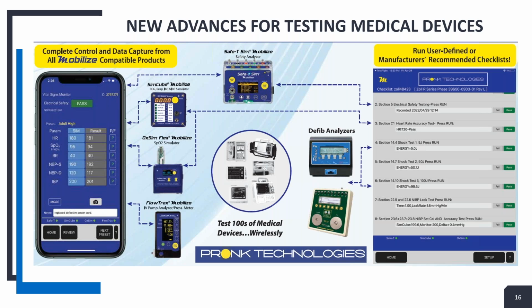And this is a basic thing. This is capturing the serial number and the calibration date of the test equipment. So in this case, it's going to pull via Bluetooth. Okay, give me your cal date, because I want to add that in a report. So not only is it doing the testing, but it's also capturing the calibration date of all your test equipment, and that'll be on each report. So you just tap on pass and then hit more, and then hit done, and it goes on to the next test.